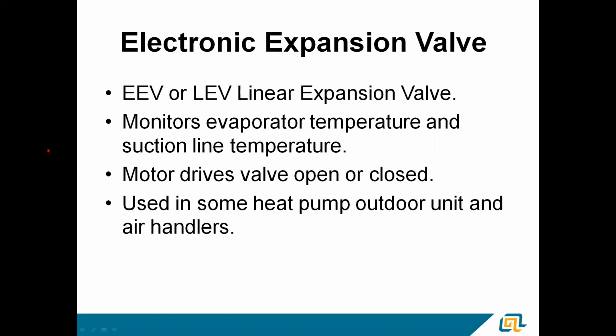There's also some electronic expansion valves out there. They can be referred to as an EEV or an LEV. Either one, it's the same thing. Monitors evaporator temperature and suction line temperature to maintain superheat. TXV kind of actually monitors system pressure. That's one of the closing forces on the valve. The LEVs, they're strictly monitoring temperature, and they drive open and closed based on that. They're used in some of the outdoor units, the heat pumps, and there are air handlers with them as well. The higher end air handlers, TAM 7s, 8, 9, they all have an electronic expansion valve.